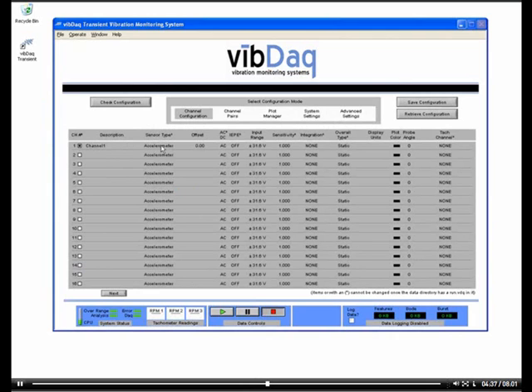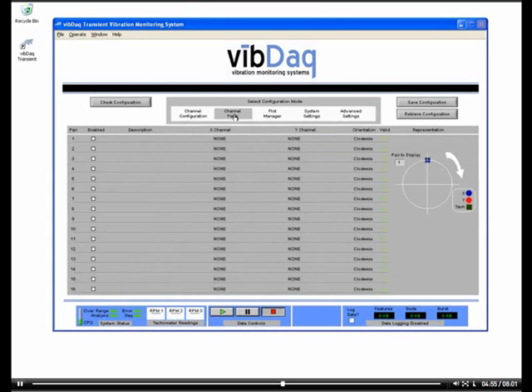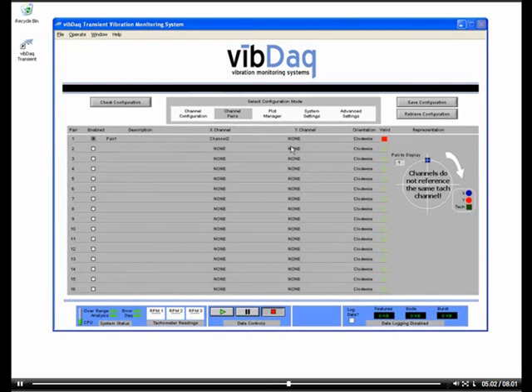There are a variety of configuration options for the input channels, including display units, sensitivities, AC or DC coupling, and IE-PE to provide excitation currents to accelerometers if needed. Once hardware input channels have been defined, we can group sensors located at the same point on our machinery into pairs. These pairs can be used for certain plots like orbits or shaft centerlines for insight into the two-dimensional motion of our machinery at that point.